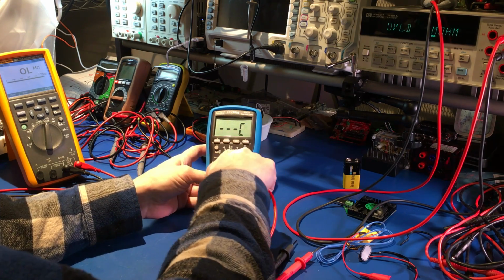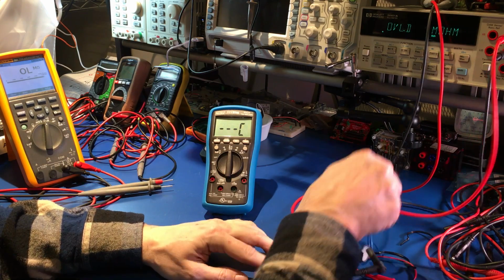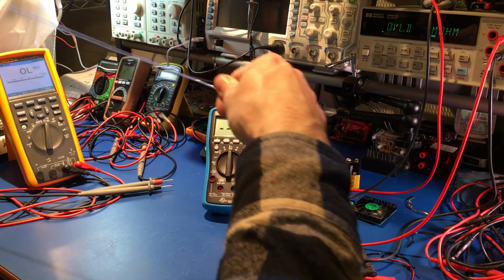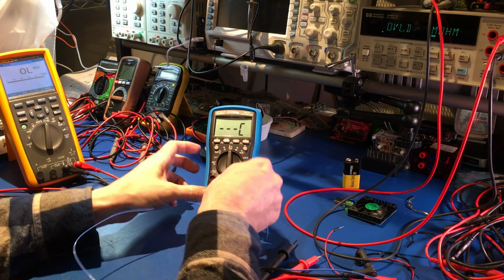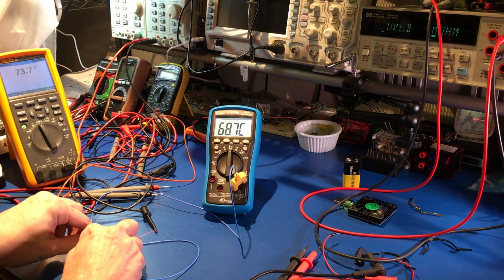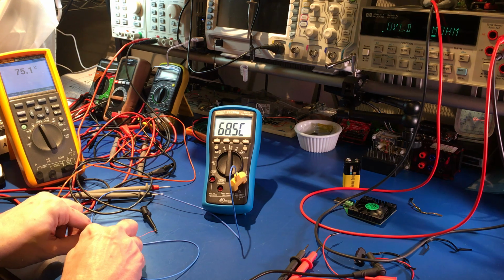I don't know how I want to set up this for checking the temperature. There we go. Unwrap this guy. So 73.6 versus 68.7, 68.8, and it's still not done warming up. I can tell by the amount of milliamps it's drawing right now that it's still climbing. It should go down to about 9. Oh, nope, it just reset. You can tell when it flips on and off there.